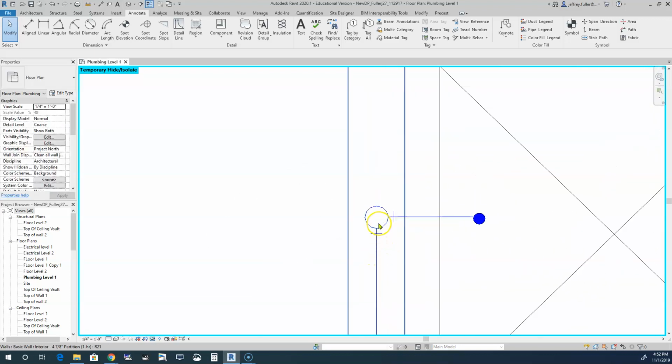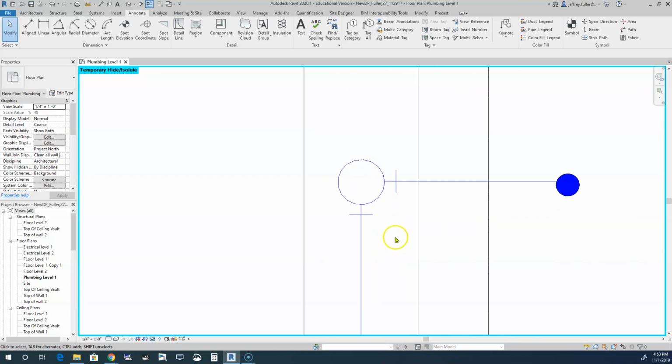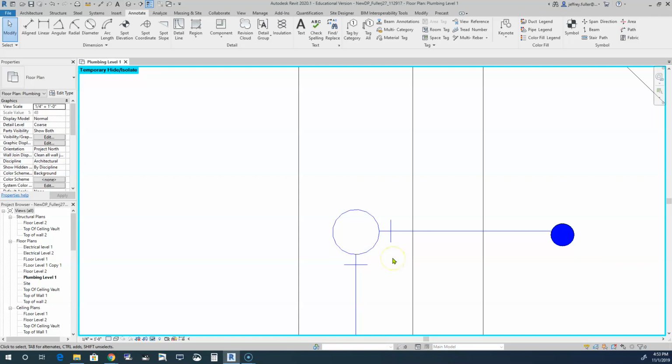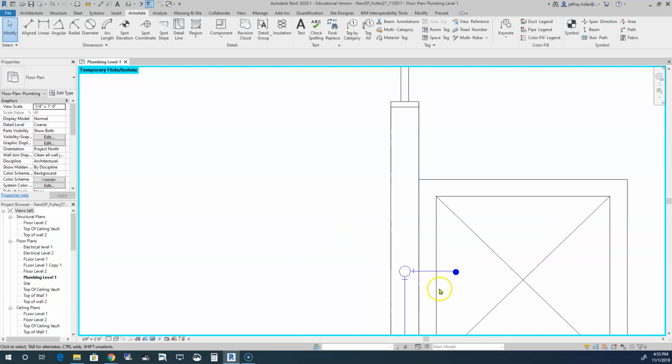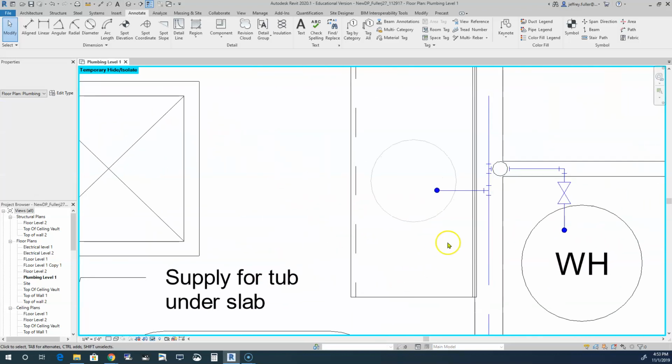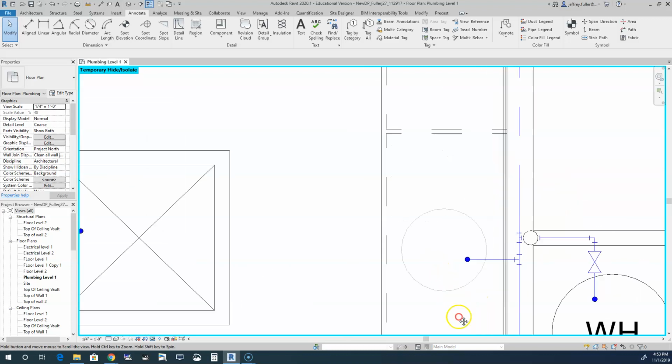All right, and then going to the shower. Here I just have a series of 90-degree elbows. Now my pipe for my shower is going to come here and it's going to turn upwards, and that's what this solid circle represents, is basically my up pipe. Regardless of the size of the pipe it is, I just draw a 1-inch circle to represent the up pipe. There's actually a different circle that you use to represent down pipe. Down pipe would actually have a segment cut out right here with the line extending into it. And I really could have drawn this either way, but I wanted to start with the direction that the water was going and do it that way.